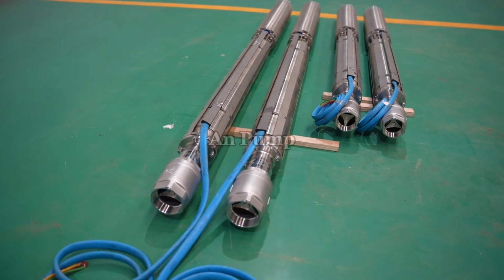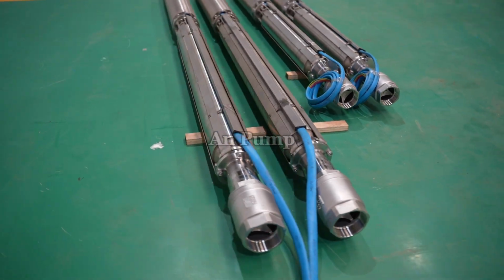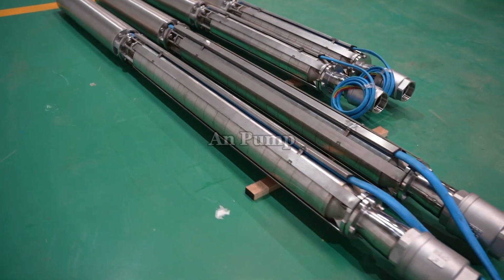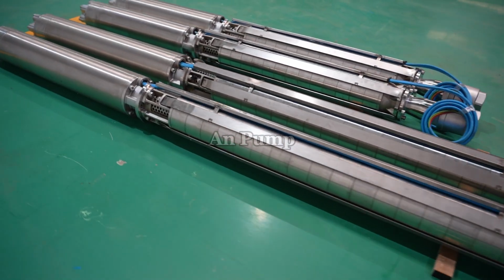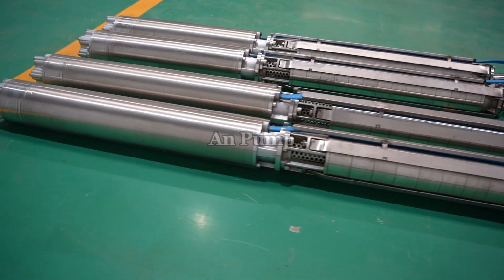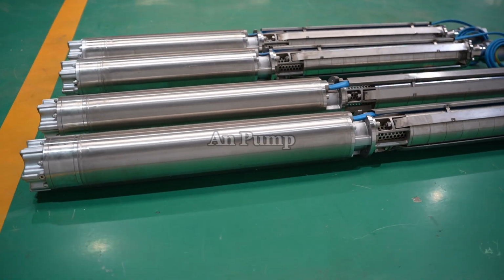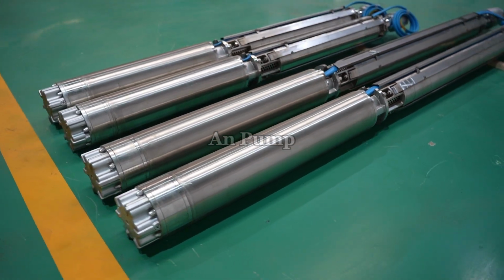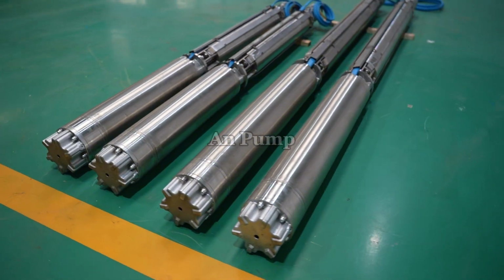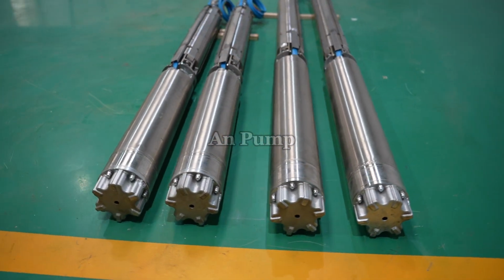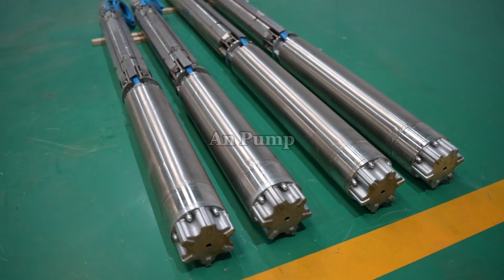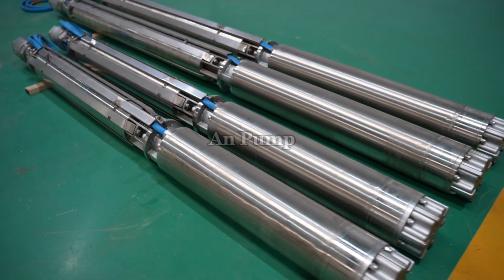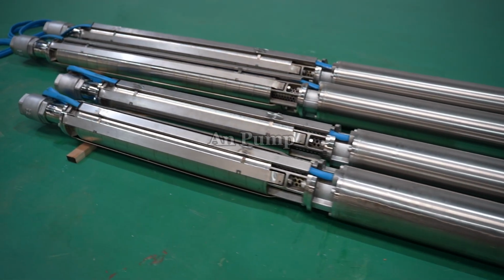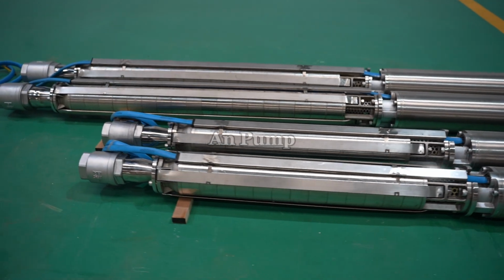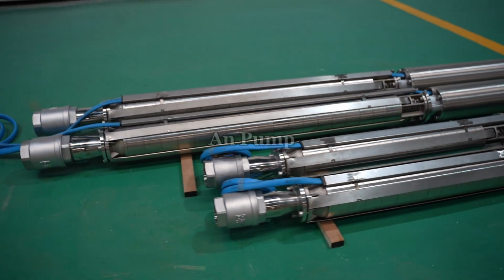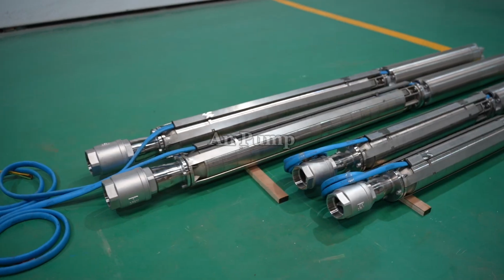Finally, type number 5, the submersible centrifugal pump. These pumps are designed to operate while fully or partially submerged in the fluid they're pumping. The motor and pump are hermetically sealed in a single unit and lowered into a sump, well, wet pit, or body of water. Because the pump is already immersed, it's always in a flooded suction condition. That means no priming is ever required, and cavitation risks are much lower compared to pumps that have to lift water from a lower level.